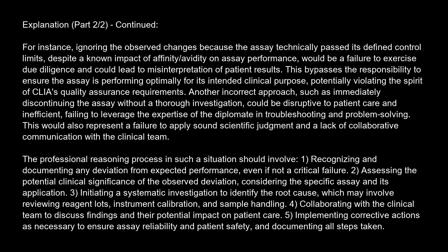3. Initiating a systematic investigation to identify the root cause, which may involve reviewing reagent lots, instrument calibration, and sample handling. 4. Collaborating with the clinical team to discuss findings and their potential impact on patient care. 5. Implementing corrective actions as necessary to ensure assay reliability and patient safety, and documenting all steps taken.